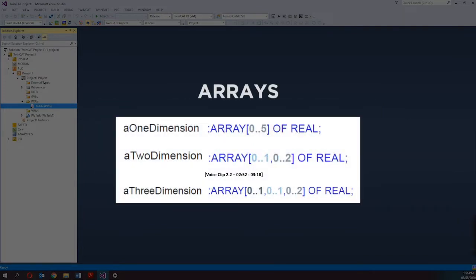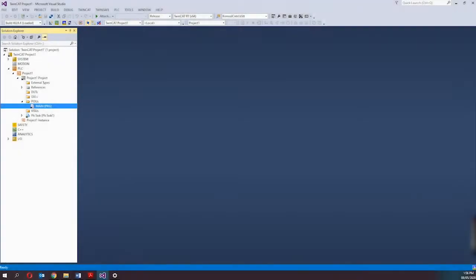Arrays are also supported in TwinCAT 3. One, two, and three-dimensional fields are supported as elementary data types. Arrays can be defined both in the declaration part of the POU and in the global variable list. In addition to standard data types, you can define your own data types such as structures, enumerations, references, and unions.